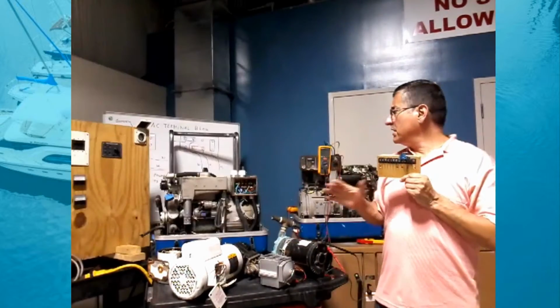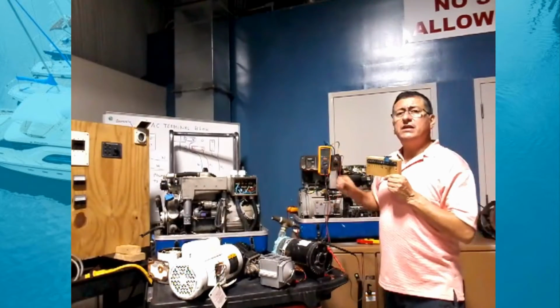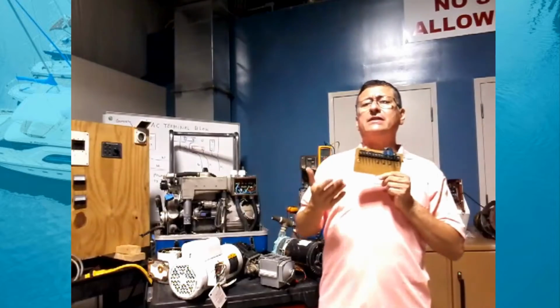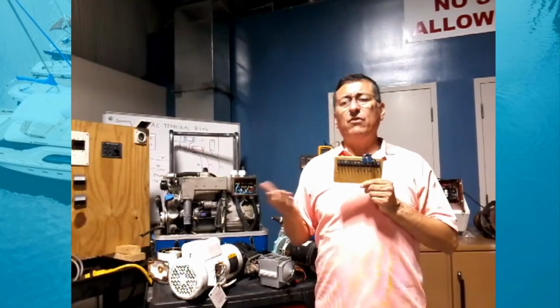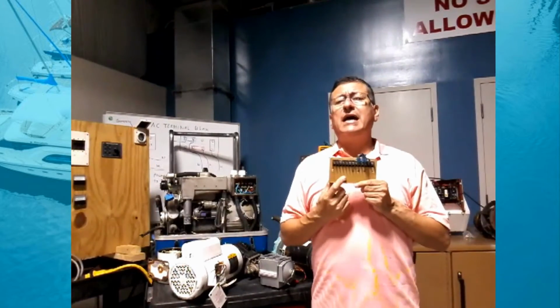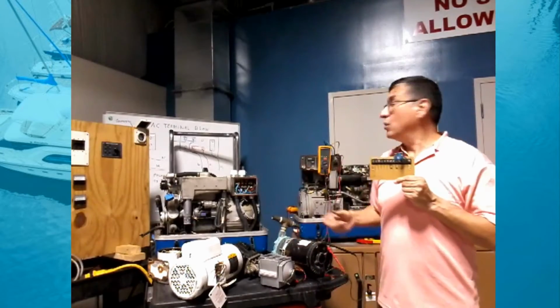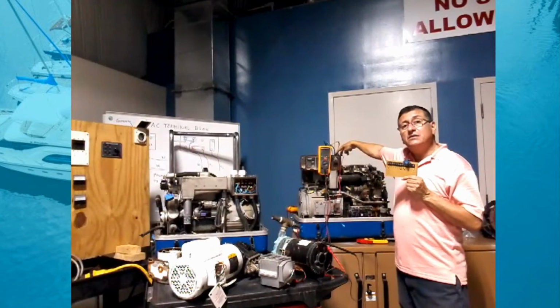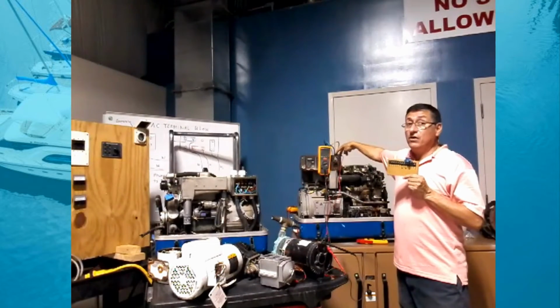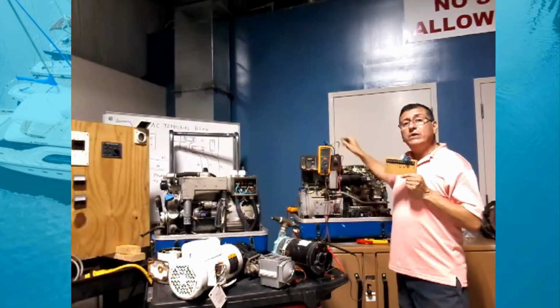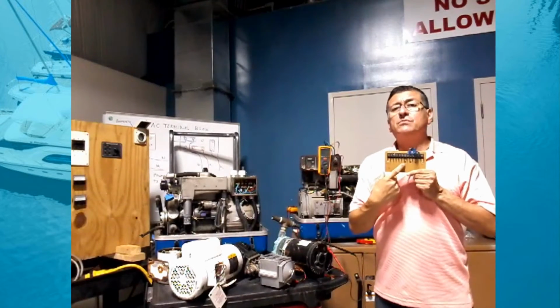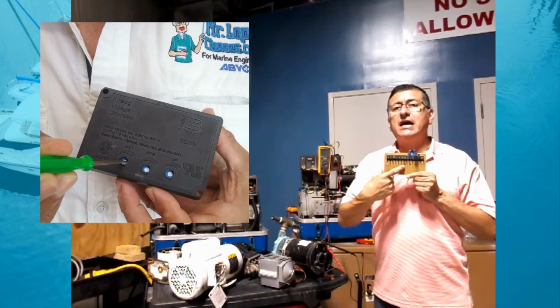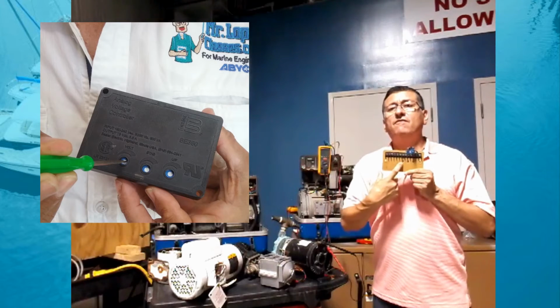For example, at this moment, the reading on my voltmeter is 127 volts, 128 volts. It's a little higher. I can adjust, of course, with the engine running. I connect my voltmeter to the terminals of the breaker, and with the generator running, using a small flat screwdriver, I adjust the voltage pot.